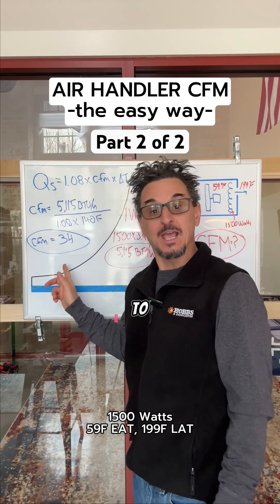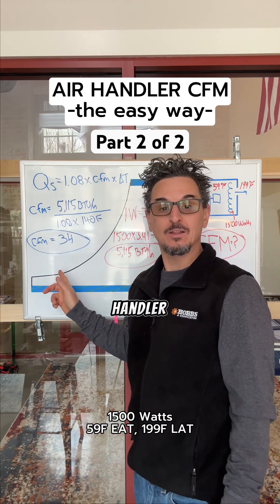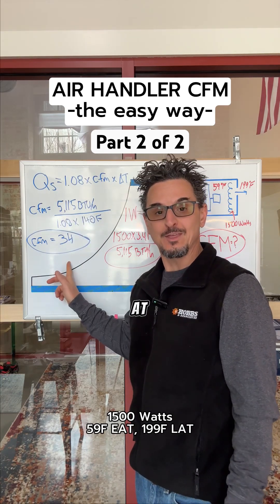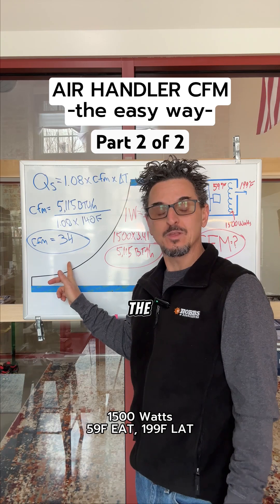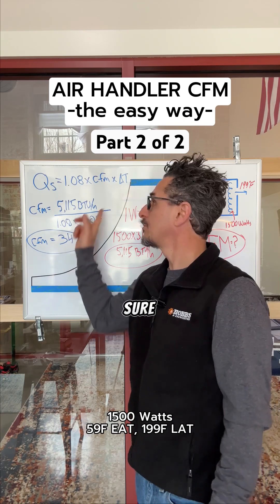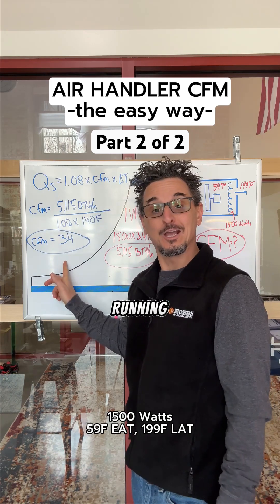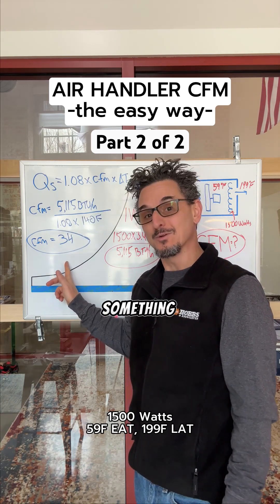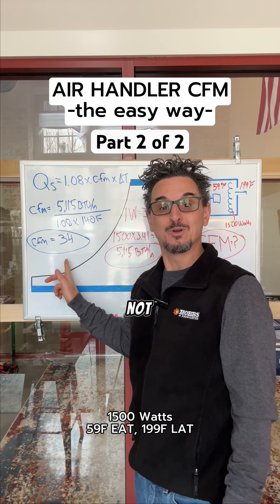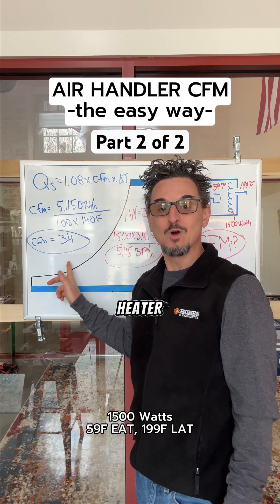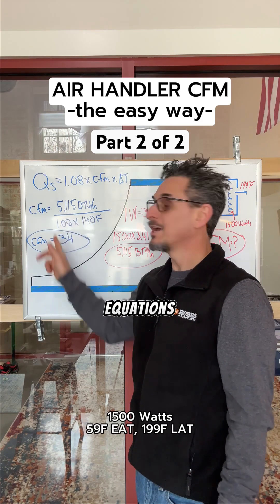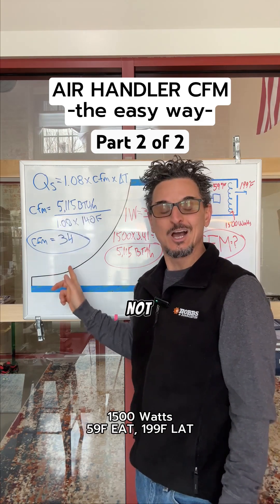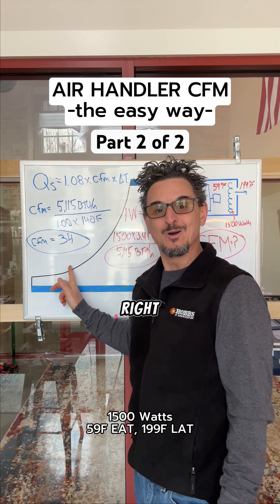You can apply this principle to any air handler. If you're looking at the nameplate KW of the heater, make sure the heater is running on all stages and that there's not something wrong with it — because if you're not producing the heater wattage, this equation is not going to come out right.